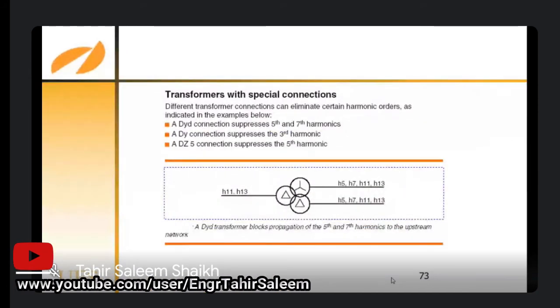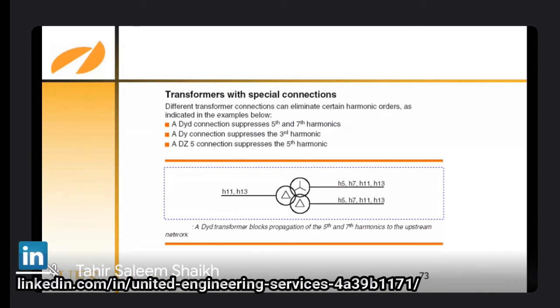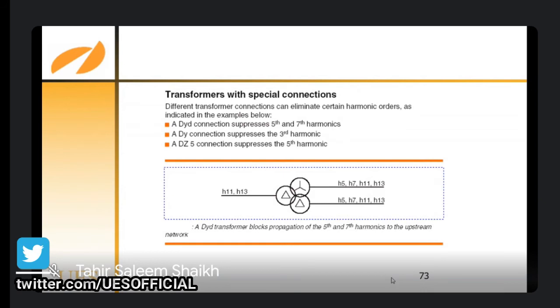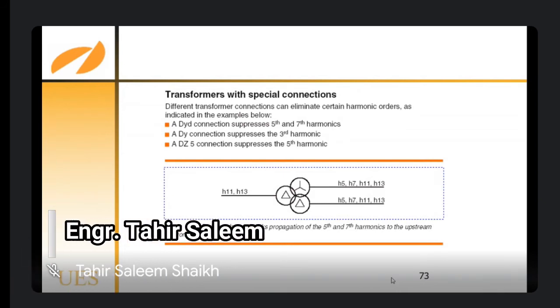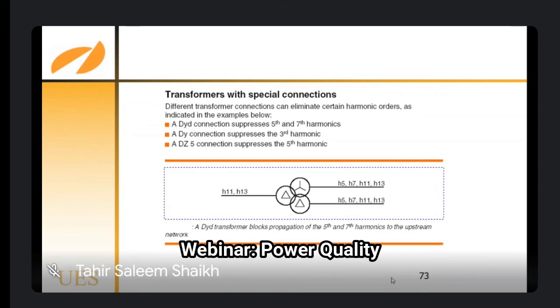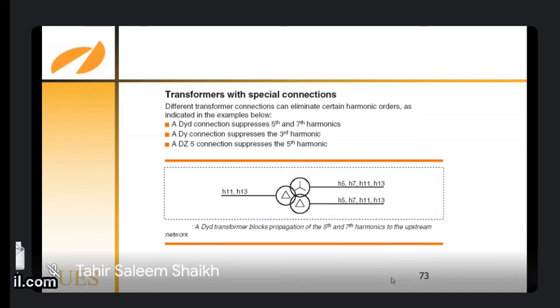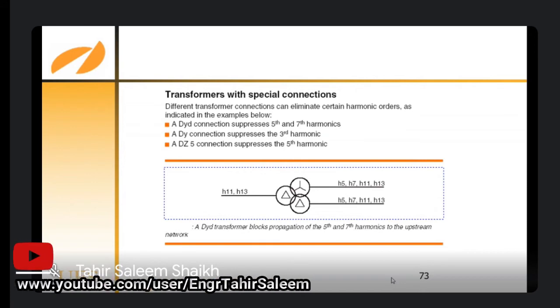Now the third solution is special transformer connections, in terms of vector groups: a Dyn connection, a DZ zigzag connection, a delta star connection. They suppress the harmonics level. But I have seen so many places where you have to decide by yourself what the solution is. And this is also very expensive, and these transformers have to be specially built for harmonic suppression. That's why, when you are designing, and as a maintenance engineer, separate linear loads and non-linear loads, and feed them accordingly as per requirements or recommendations.